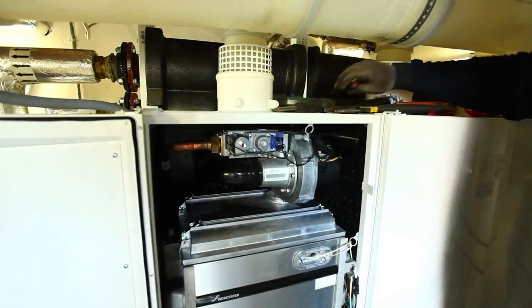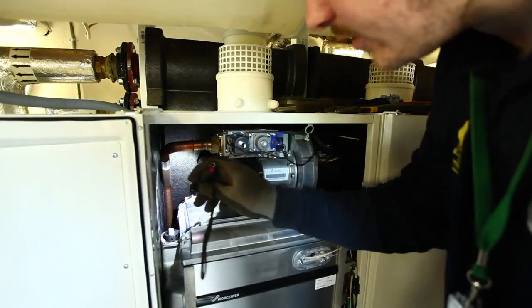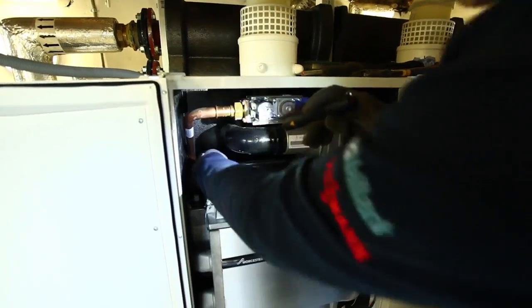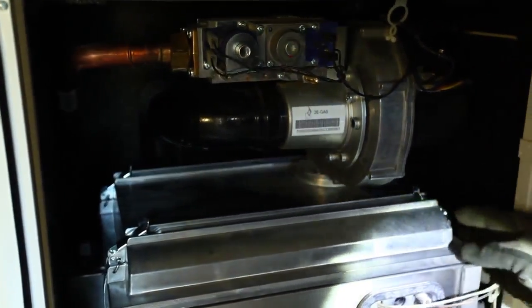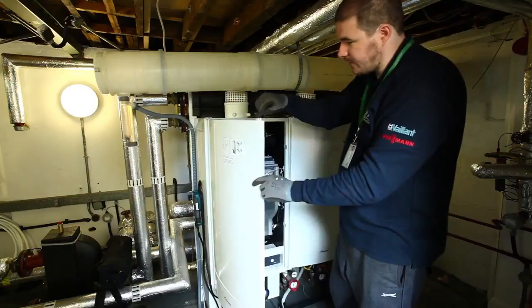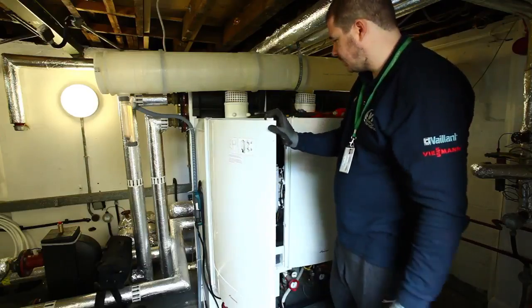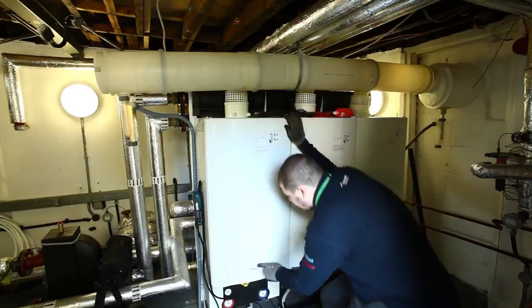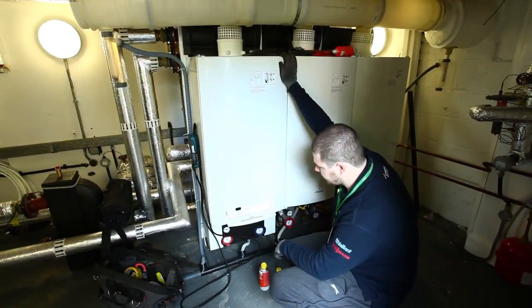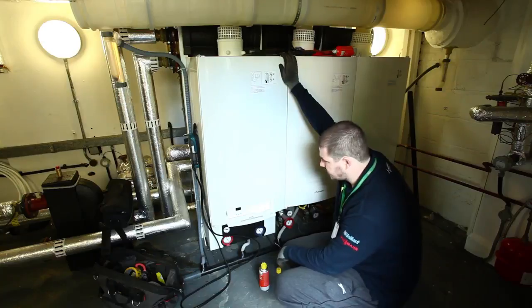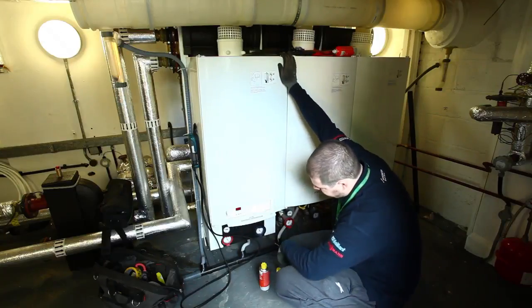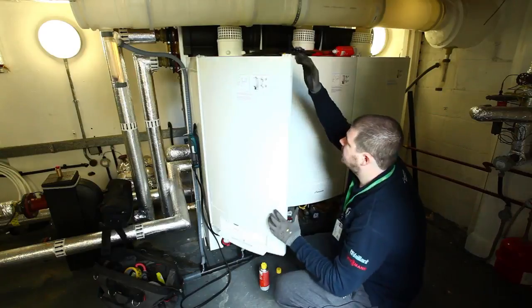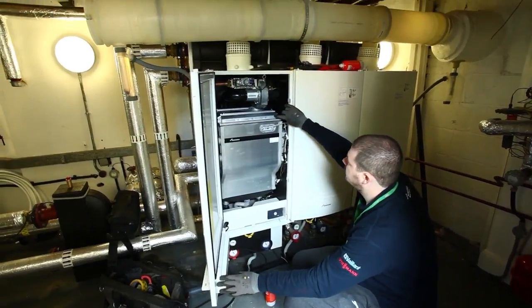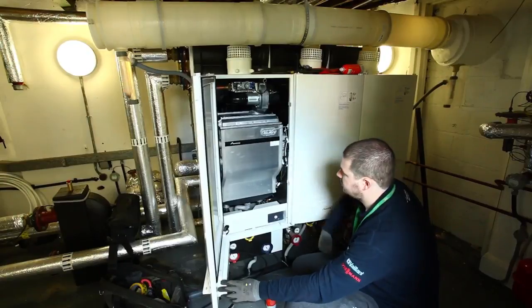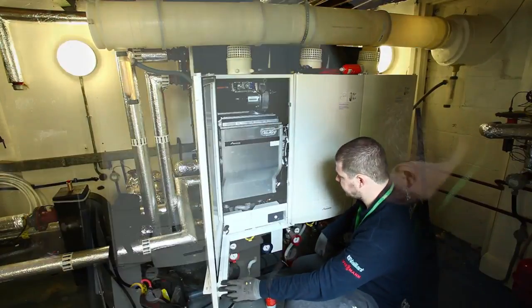We're just going to inspect the combustion chamber to make sure all the clips are in the right relevant locations, so we're not going to get any rogue flames coming out the back of the boiler, which we don't want. Keep the door open on this nice little latch they have for us for testing and commissioning purposes. So once we're happy with the gas, all the wires are plugged into the right locations and the gas has been tested for leaks, we're then safe to return the gas and the power back to the boiler. It starts off with a little initial purge, just to clear any gas or any residual dust that may be in the boiler, clear it out.